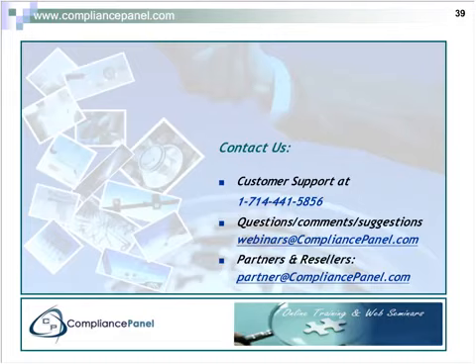The only things that are more enhanced would be the customer complaint process. You wouldn't see that in 9001 as heavily as it would be in 13485. If you're marketing direct to clinical use devices, the MDR, the medical device reporting process, much like the vigilance process is for Europe, I'm not sure if you're familiar with that, would be how the FDA would expect you to handle your complaints. That's the only thing I see as different. But again, you can get those requirements right out of 21 CFR 820 without going through 13485.